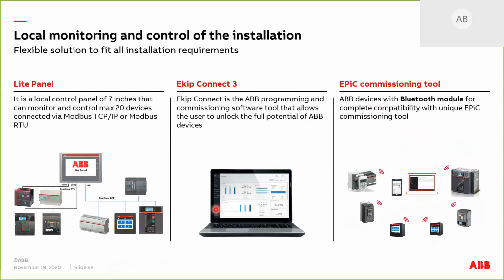All of this can be commissioned with the Ekip Connect 3. You can commission all the parameters using your laptop, or with the Epic commissioning tool, which is available for download on the Play Store and App Store. With the new product line, Bluetooth is embedded directly on the MCCBs and on the ACB with the black trip unit. As of now there are two types: the gray and the black trip unit, and the black one has embedded Bluetooth.